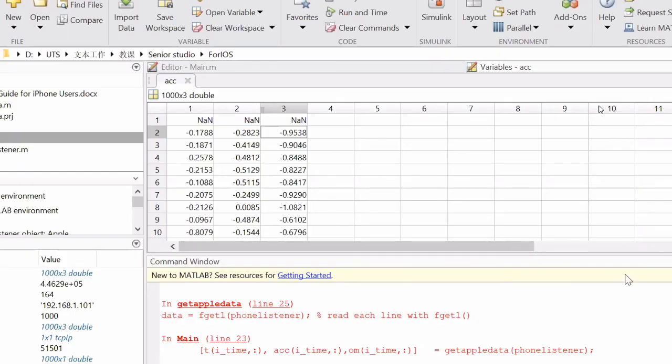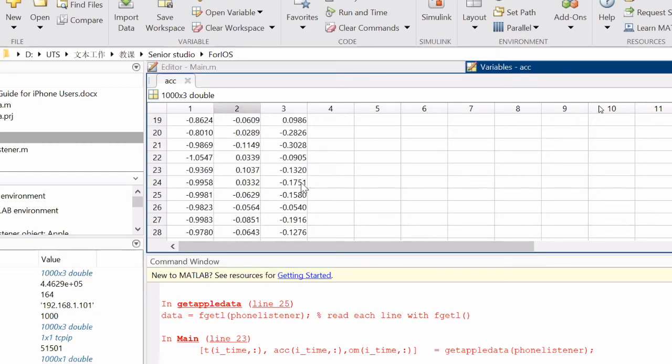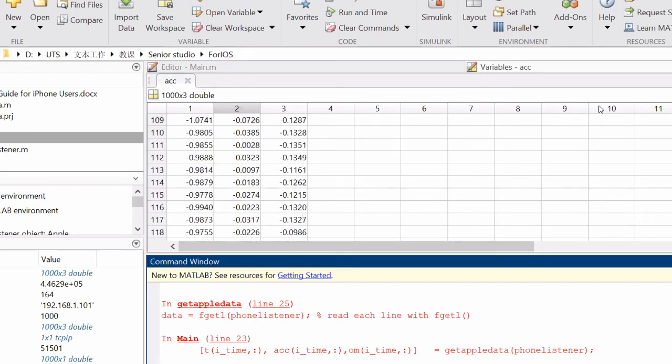I stop sharing. You pick one of them to see, but you need to be not moving. When you are not moving, you select one of these to calculate. This is data we just collected. So I'll take this as an example. You can see, my understanding is it's very close to 1. So this accelerometer is well calibrated, so there is no need for recalibration.